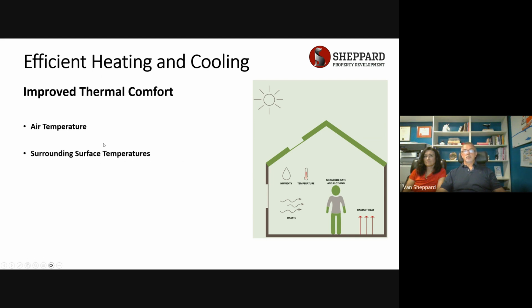Your surrounding surface temperatures, and that goes to radiant heating. So if your glass is cold and you stand close to it, you're going to feel cold. If your floors are cold and you're walking around with bare feet on, or even without bare feet sometimes, again, you're going to feel cold. If you don't have good R values and your wall temperatures are low, you'll notice that. So you want your surrounding surface temperatures to all be in a range that your body finds comfortable from a radiant perspective. Humidity matters. Too humid is uncomfortable.